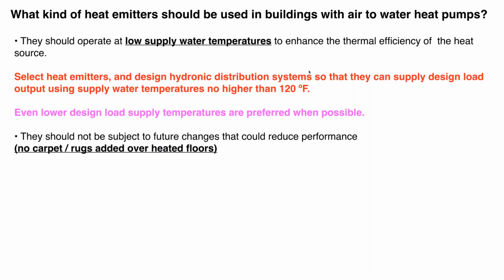one of the things obviously you want to think about too, if you're dealing with floor heating, one of the downsides or potential downsides of floor heating is you design the system, let's say for a tile floor, and somebody says, oh, I don't like the tile anymore. I want to put down a nice thick Berber carpet and a 1/2-inch urethane pad on there. Well, that is going to destroy the performance of that floor heating system. So that is one of the Achilles heels, I guess I'd describe it as, for floor heating. So, you've got to ask questions of your clients to make sure that as you design this system, you're not inadvertently designing for something that's going to have a problem later on, okay?